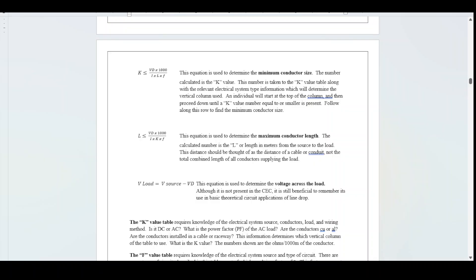The L equation is used to determine the maximum conductor length. The calculated number is L, or length in meters, from the source to the load. This distance should be thought of as the distance of a cable or conduit, not the total combined length of all conductors supplying the load. Finally, V_load equals V_source minus V_D — used to determine the voltage across the load. Although not present in the CEC, it is beneficial to remember for basic theoretical circuit applications of line drop.